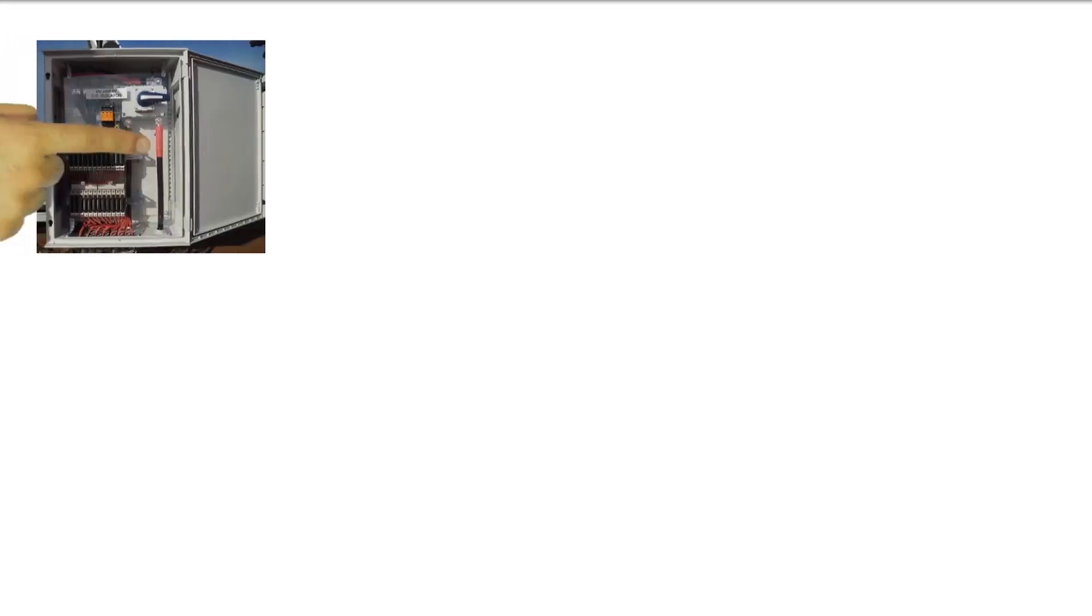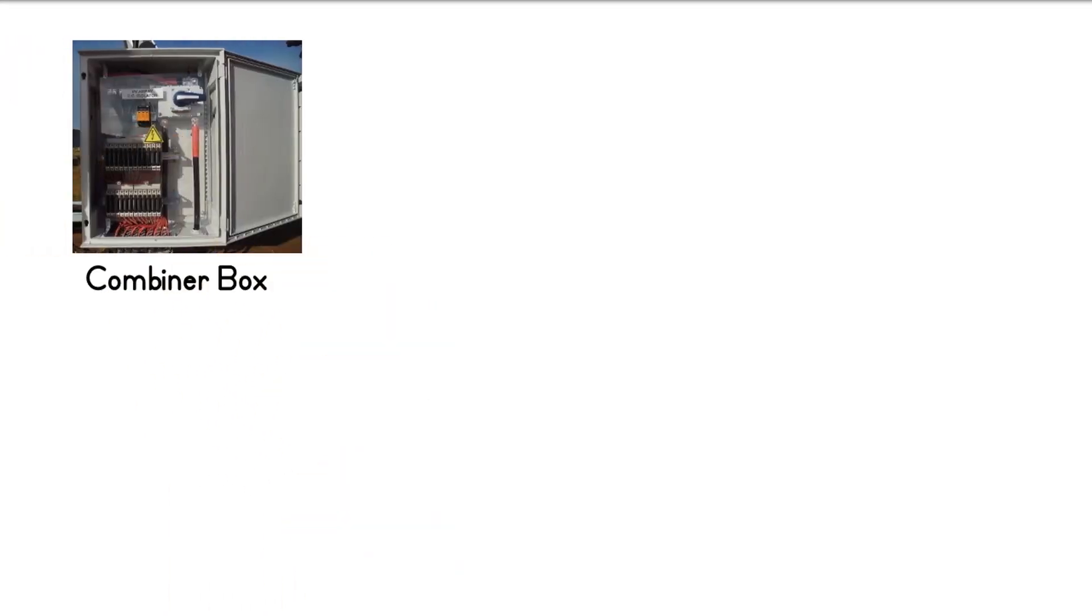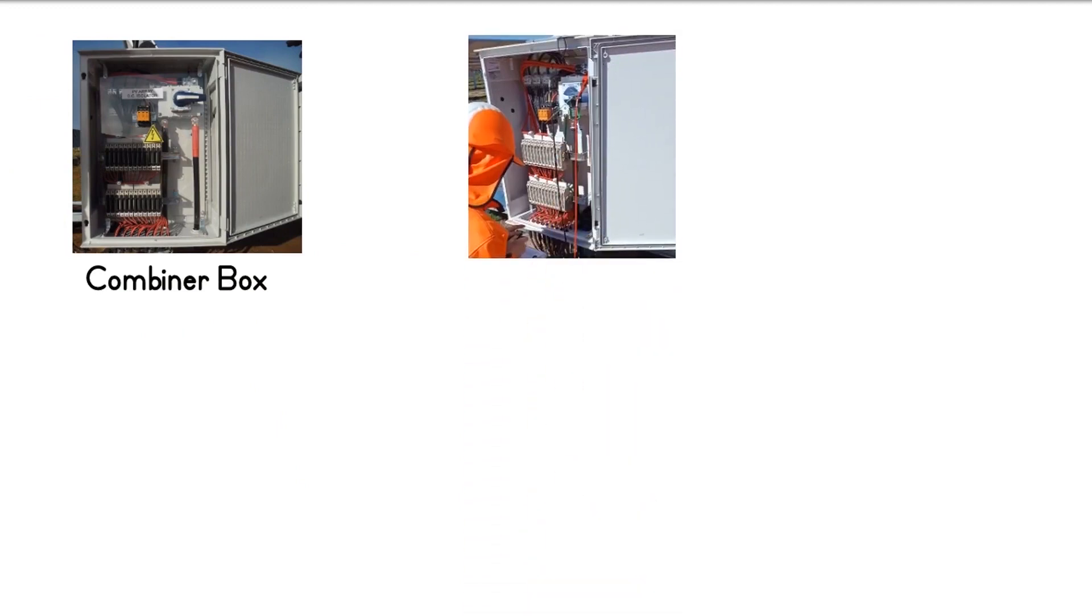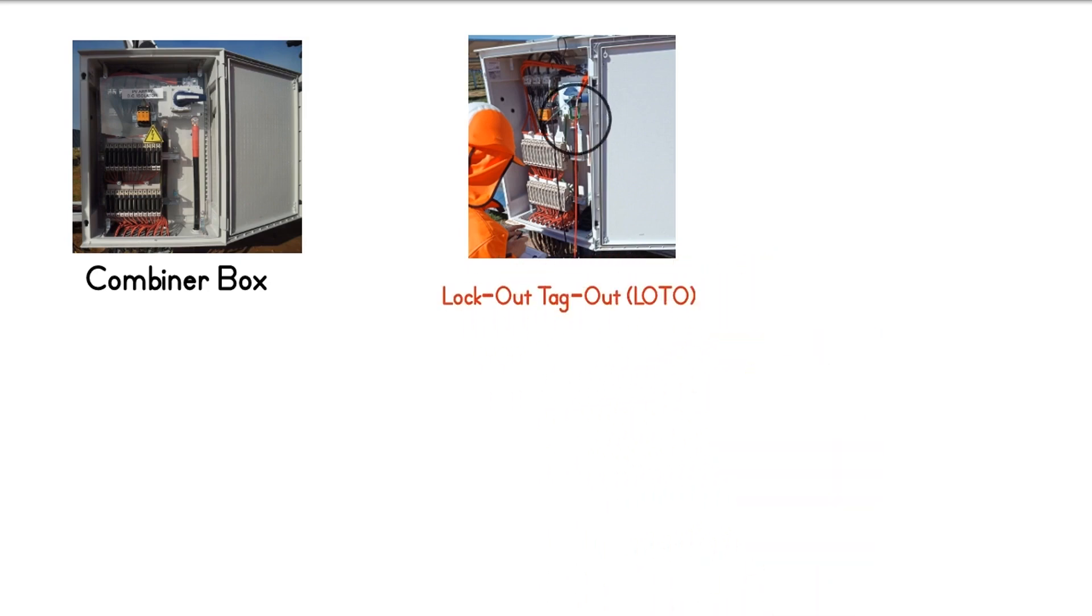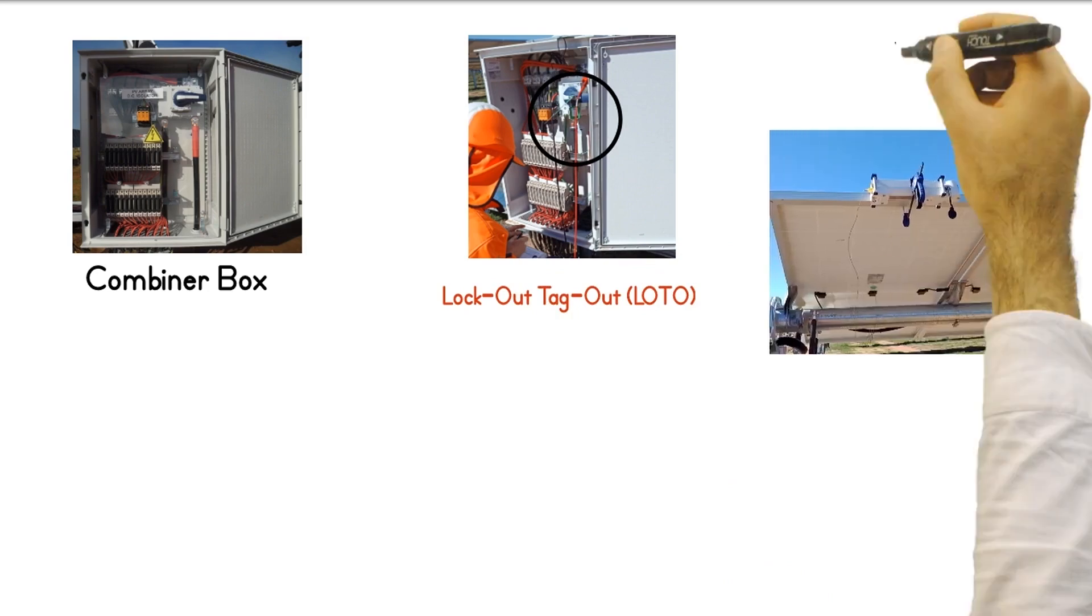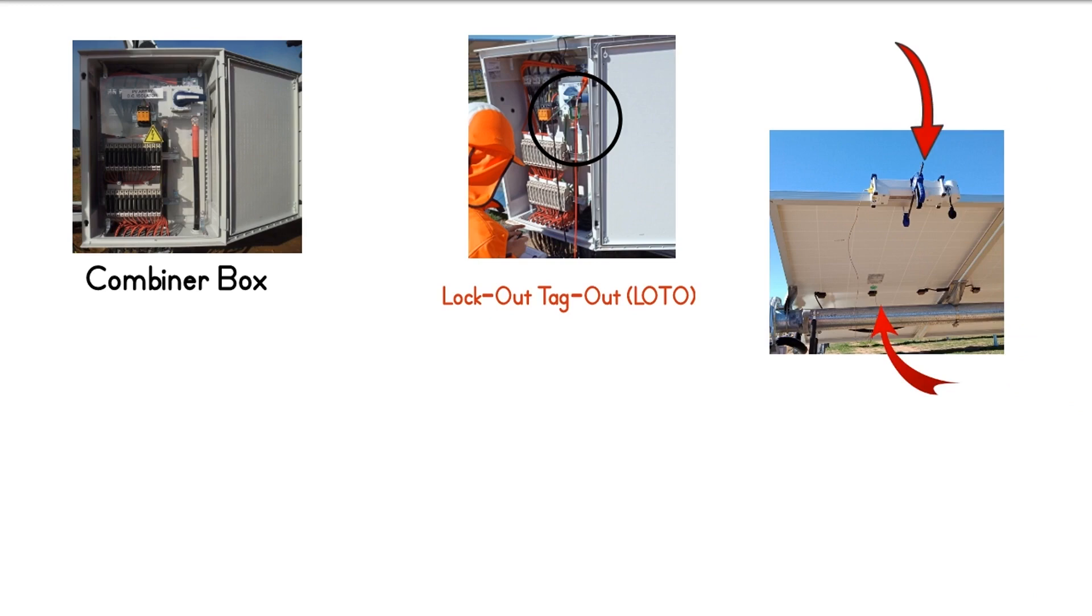To use IV curve tracing to identify underperformance in commercial or utility scale installations, the test is generally done in combiner boxes. The combiner box under test must be electrically isolated from the rest of the system. This is done by locking and tagging out the isolator in accordance with the isolation procedure in place. Install the irradiance meter on the plane of array and attach the temperature sensor to the back of the representative panel.